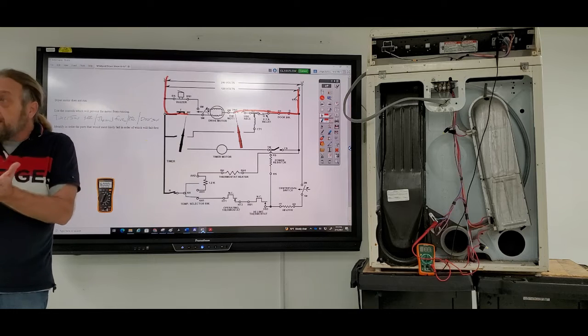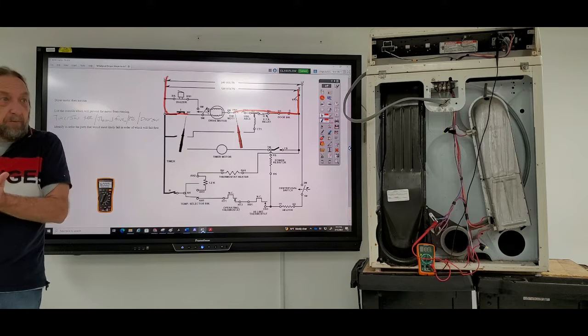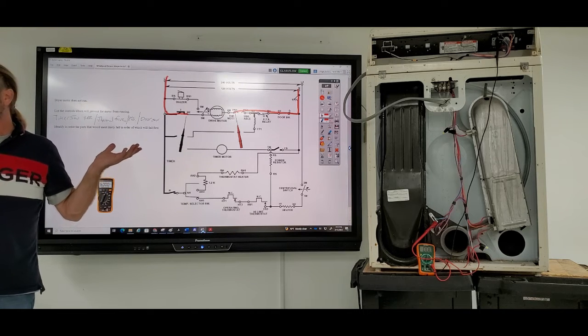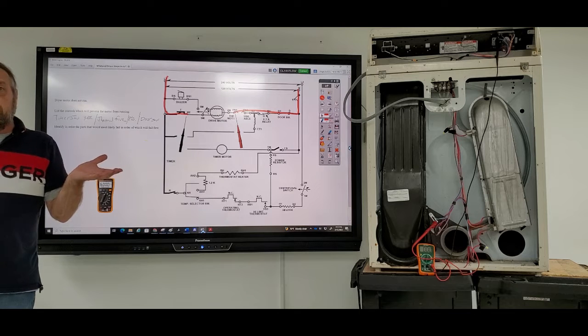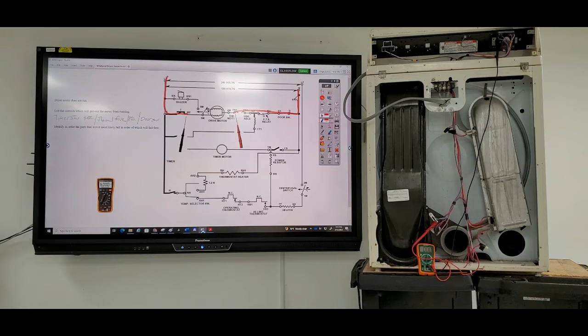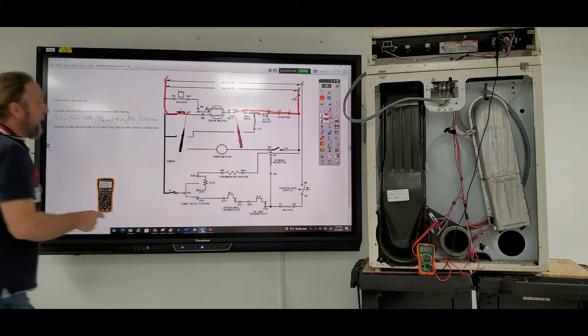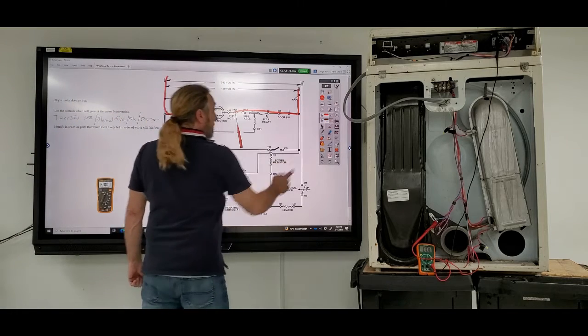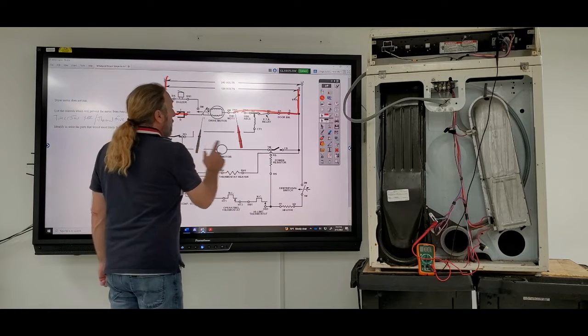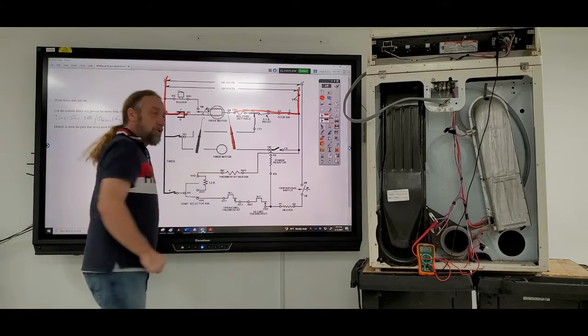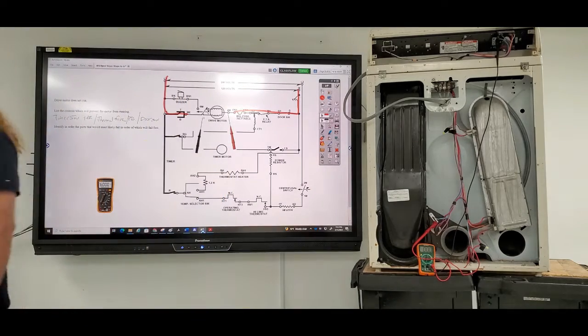The most likely problem that I have is where? In the motor. The motor itself. But what I need to do is I need to take my meter leads. Now I have to go to the motor and check to make sure I have power at the motor.